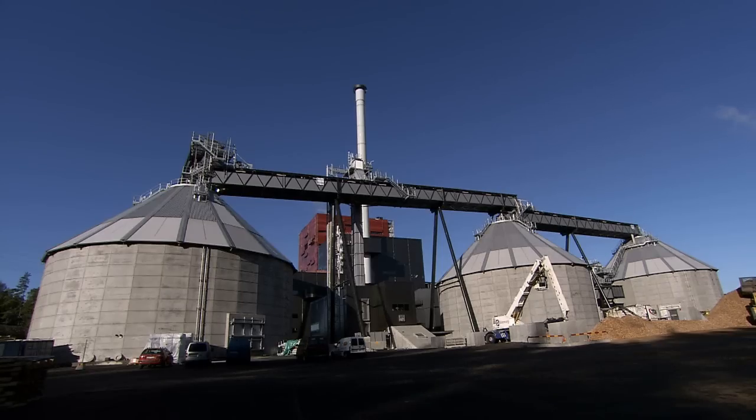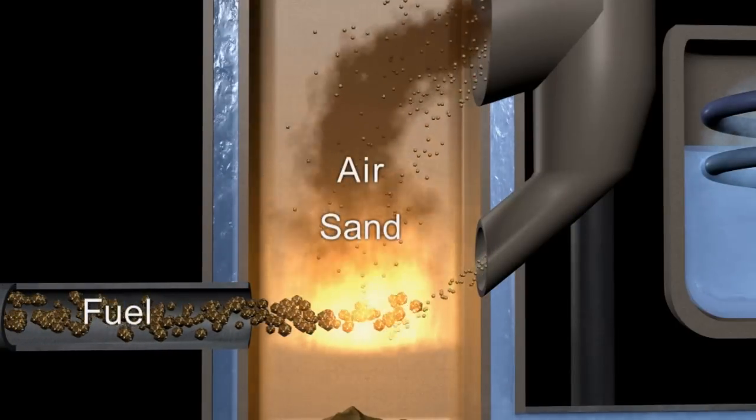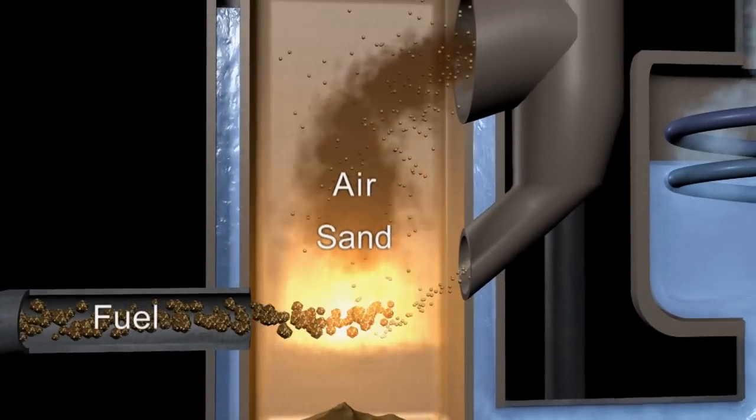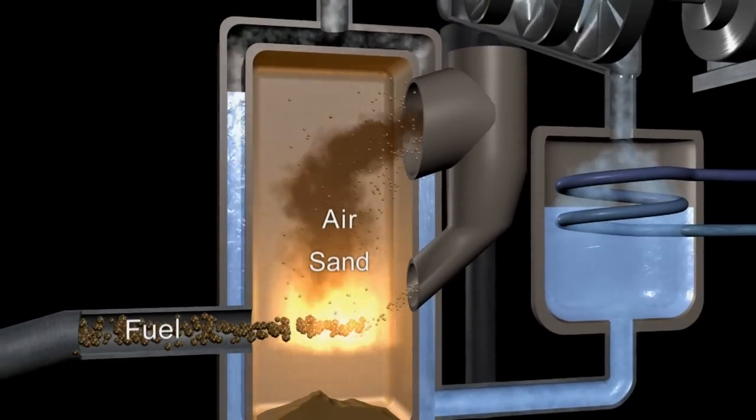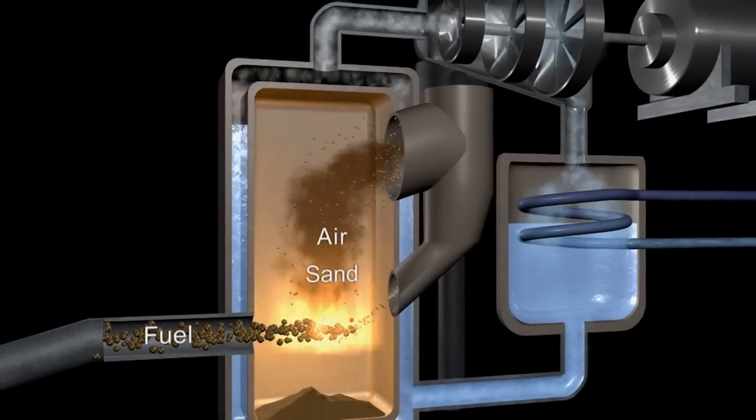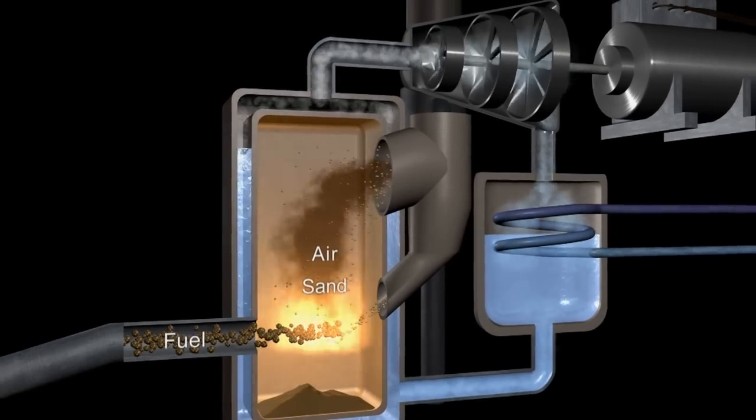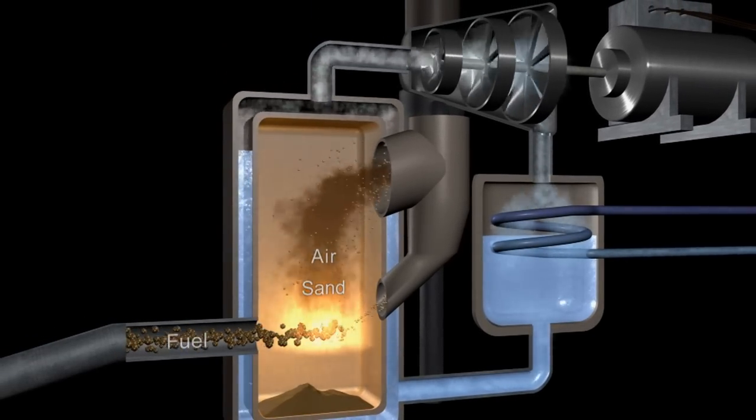Then, the process is usually something like this. Inside the furnace, air is introduced through the sand at high pressure, causing it to circulate. As the fuel is added, it mixes with the circulating sand in the air and is heated to around 900 degrees Celsius, giving it an even and controlled burn that heats water into steam.